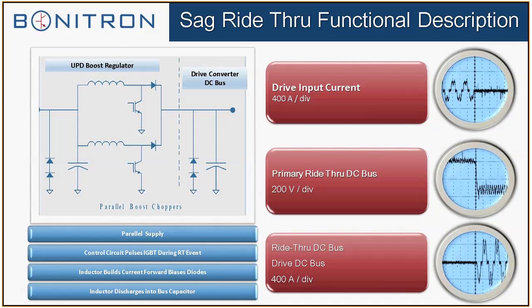So the way it works is it watches the DC bus threshold, which is in relation to the AC line. It gets to the threshold level, and then the control circuitry tells the IGBT to turn on, which starts pulsing the inductor. The inductor builds up current till it gets to a breakover point in the diode network right in front of it. Once it gets to that point, it feeds the drive bus capacitors. So pretty much we're just boosting, adding bus capacitance and voltage to the DC bus. It will keep boosting, and the IGBT will stay on until the AC line comes back and the threshold rises to the nominal level, and then you're back at normal function again.